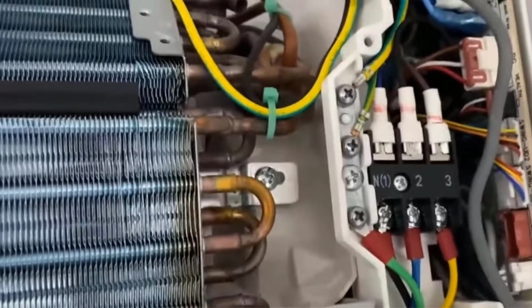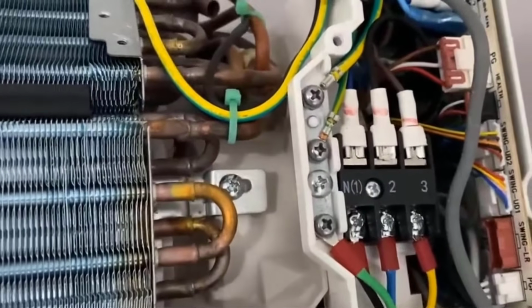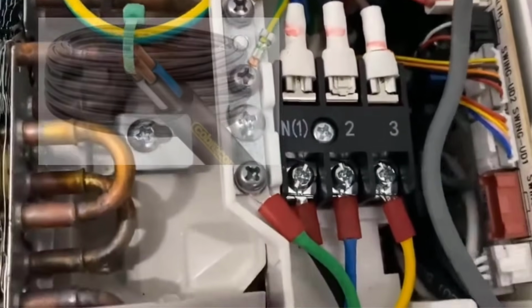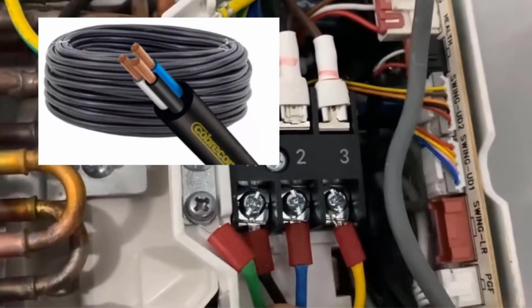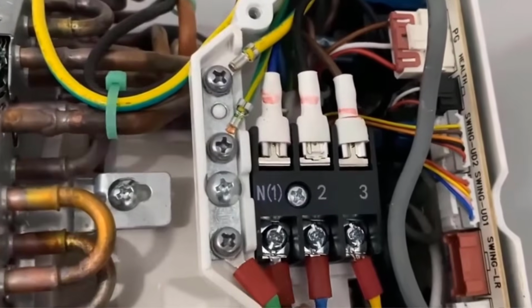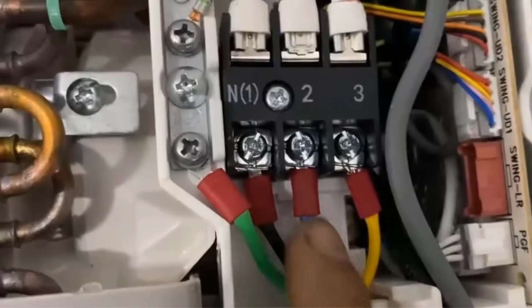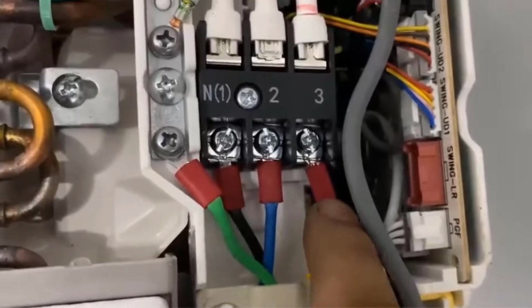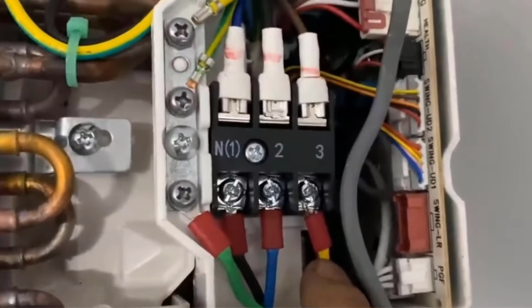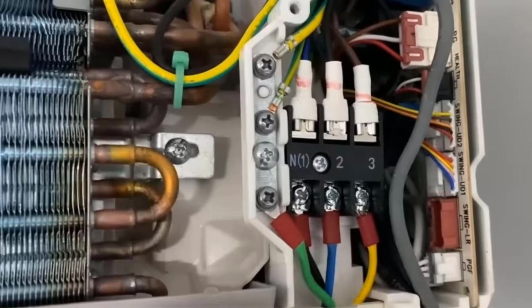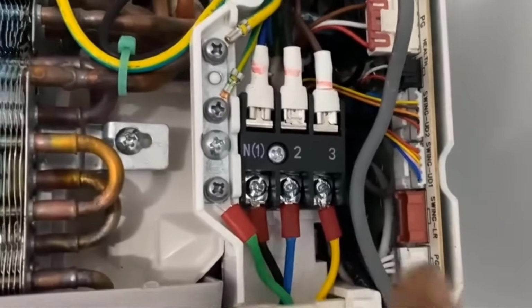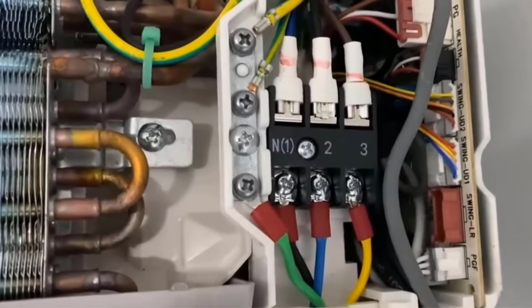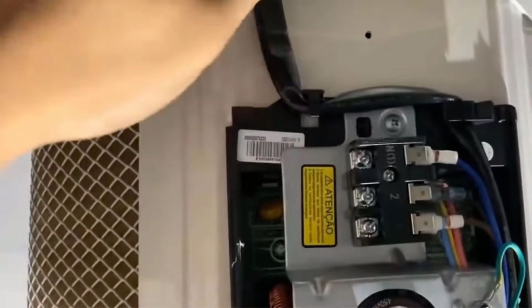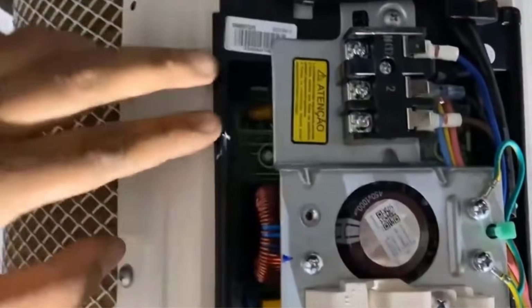Lastly, the manual mentions the cables between the indoor and outdoor units, usually a black cable with 3 wires, 2 for the power supply and 1 for the signal, marked as S. The cables must be installed with the same colors connected to the corresponding positions in both the evaporator and the condenser. If there is an error in the installation, the code C422 may appear. However, if your air conditioner was already working and the error has appeared now, it is likely that the problem is not in the communication cables. Even so, it doesn't hurt to check if any cables are loose or oxidized.